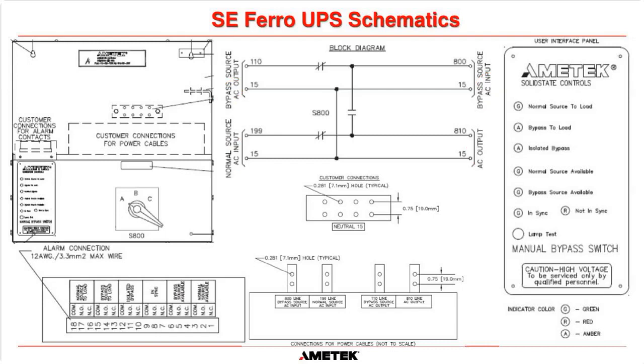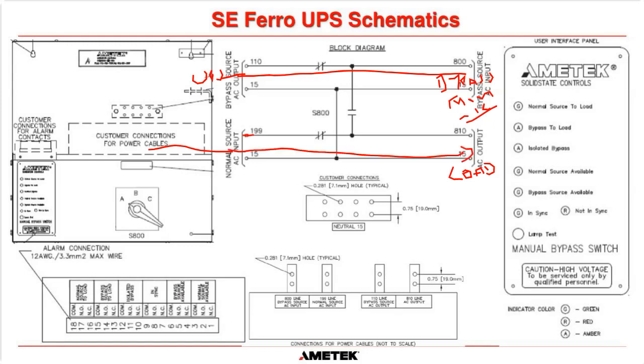We're going to see in a few slides' time that it's actually a lot simpler than you think. But this is the load. And this is the bypass from your MCC or your bypass transformer. So that's your external world. So basically, your bypass comes this way here, and then that goes to the UPS and supplies the bypass to the UPS static switch. And remember that static switch is usually off. And then the output of the inverter static switch comes back this way here and feeds power to the load. That's why in normal operation, it's shown here that this contact is open, this contact is closed. So bypass goes to the UPS this way, and the output from the UPS gets connected on this one here.